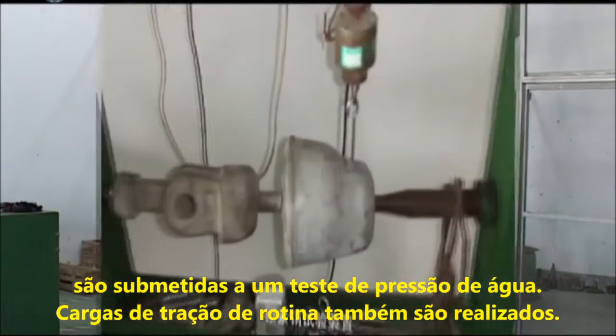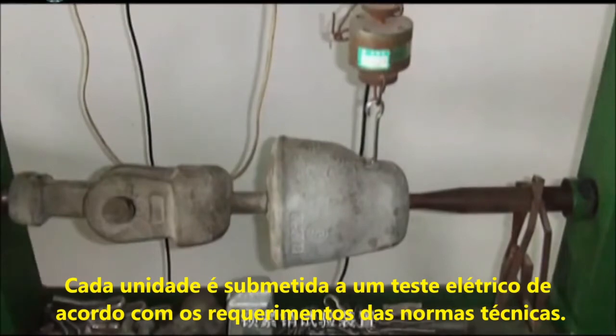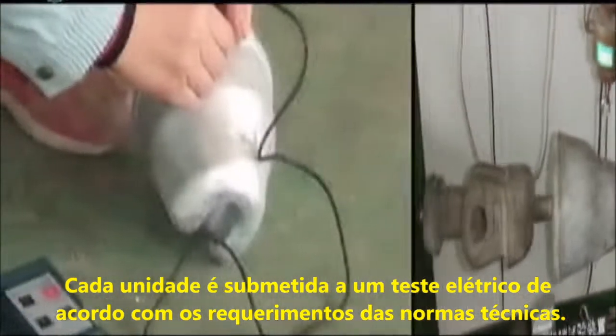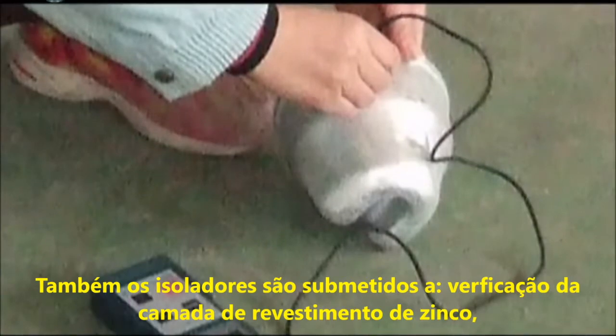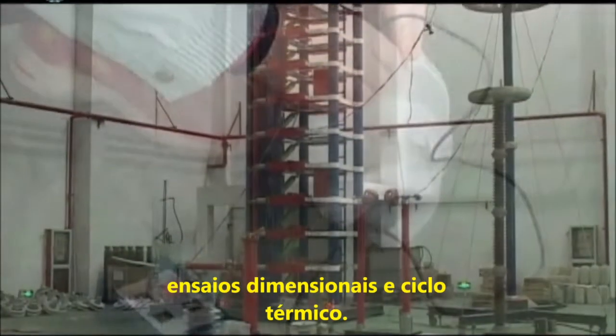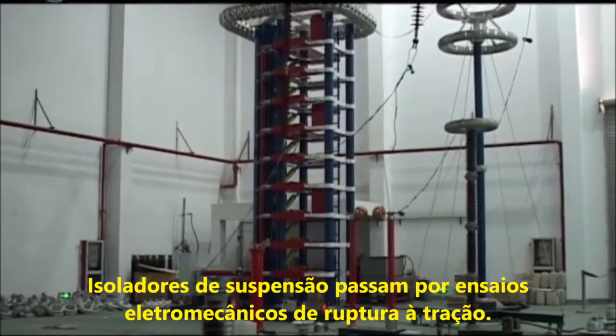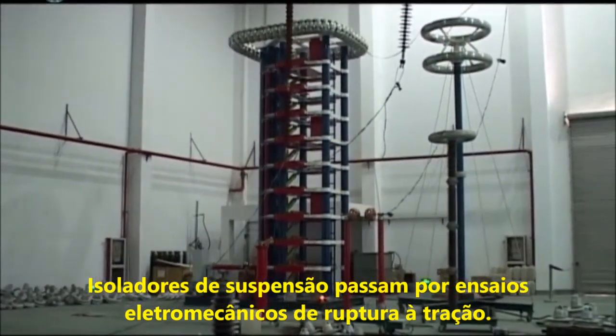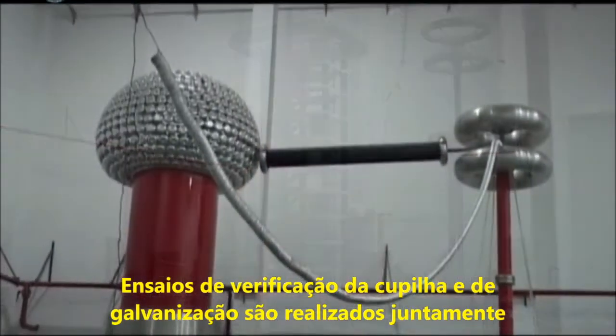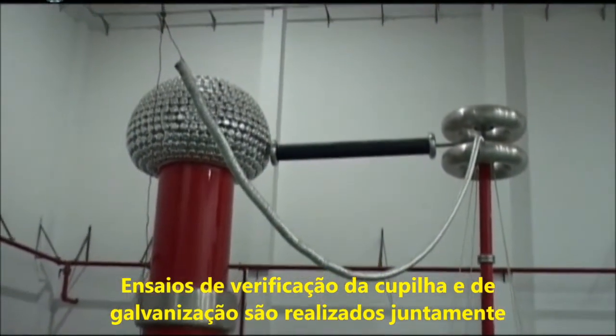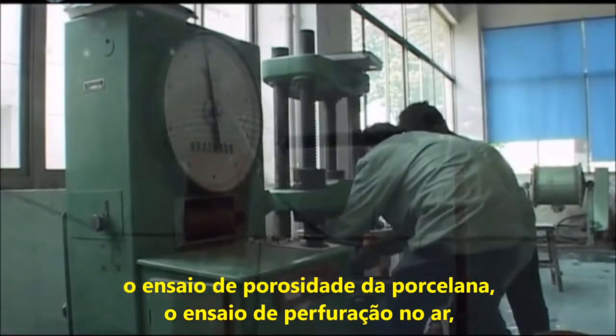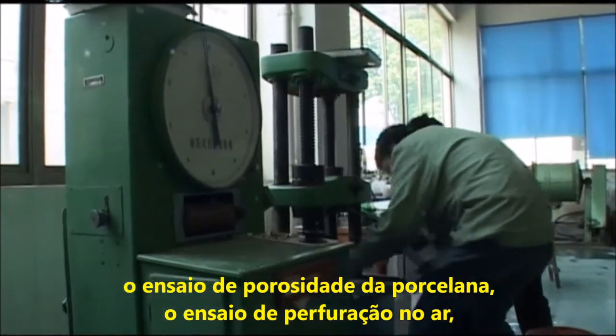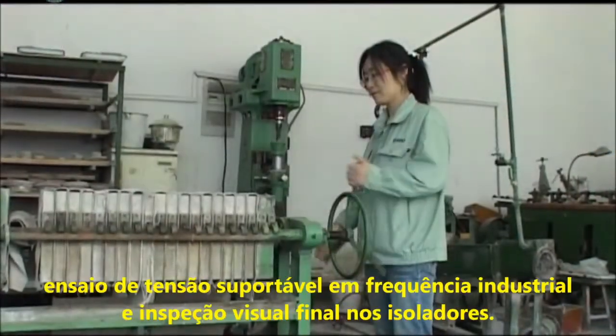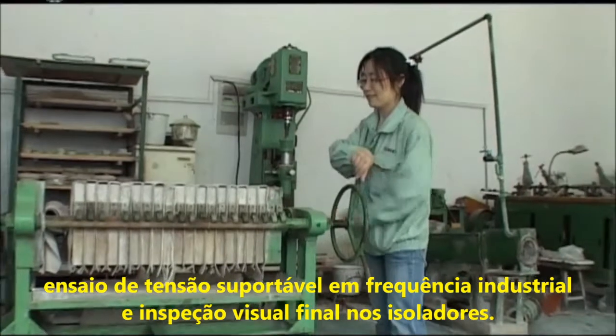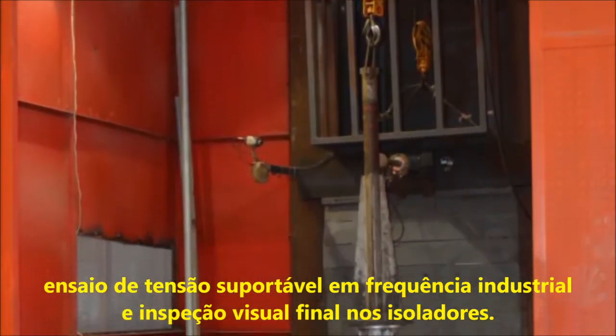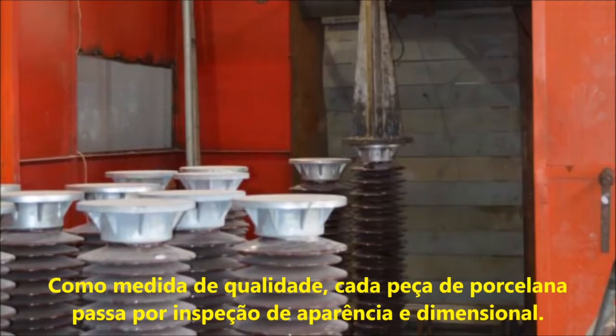Routine tensile loads are conducted. Each unit receives standard electrical testing as required by standards. Additionally, spot checks are conducted for appearance, dimension, and temperature cycling tests. Suspension insulators receive combined mechanical and electrical failure loading tests. Locking pin tests and galvanizing inspections are conducted along with porcelain porosity testing. Porcelain porosity test. Insulator impulse breakdown test in the air. Power frequency puncture withstand voltage test. Porcelain post-insulator and finished product inspection process and equipment introduction.